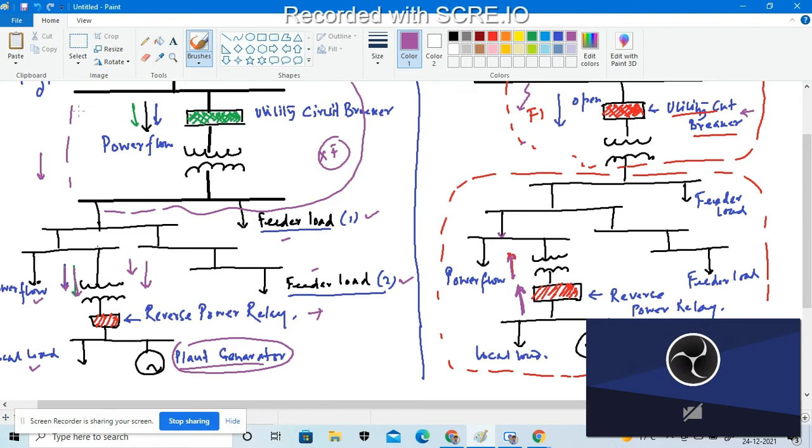So the approach associated with this reverse power relay is very useful to detect the loss of a grid due to any such kind of fault, whenever the difference between the load side and the available generation is not sufficient to obtain an appreciable rate of change of frequency.